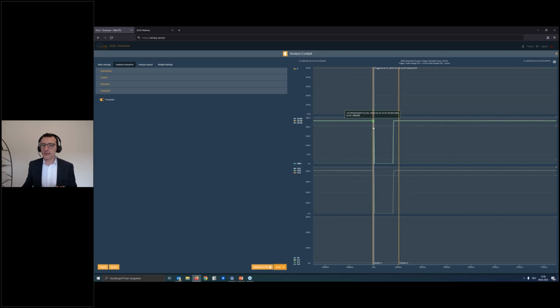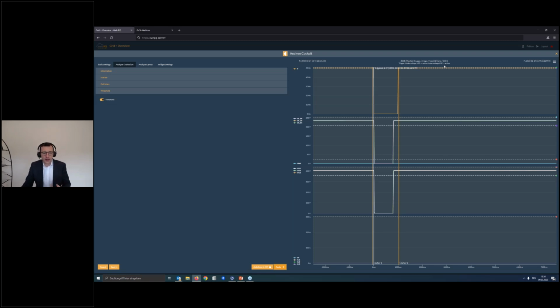Due to this situation here, this undervoltage U23, so line 23, active trigger undervoltage, this high true RMS recorder was stored inside the device and was transferred into our database system, and you can see it here in our software solution.